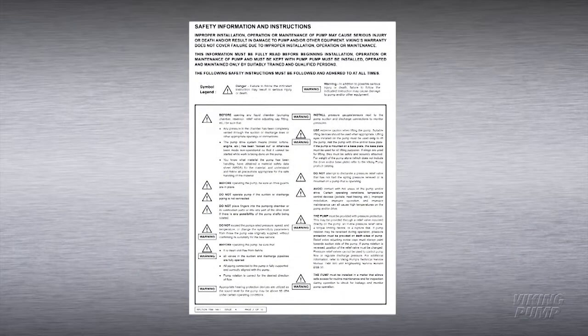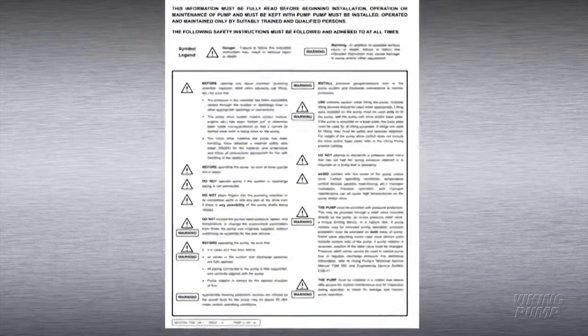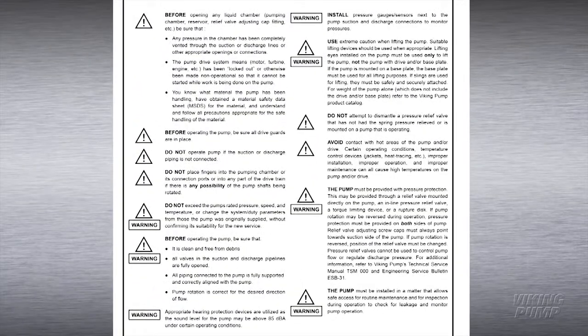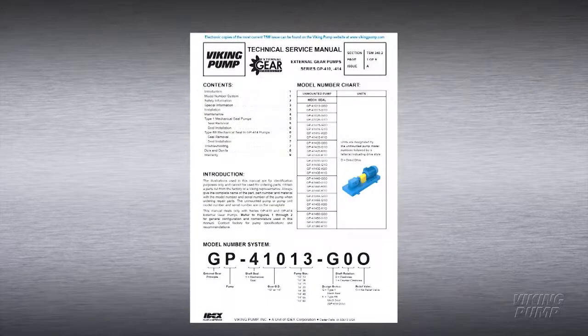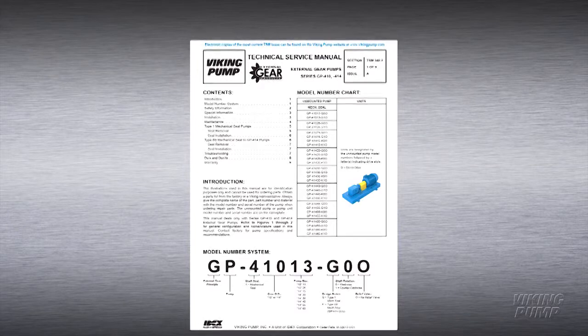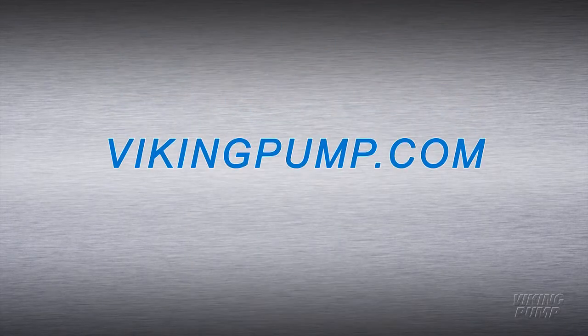As always, remember that safety is the highest priority. When working on or around any equipment, follow the correct safety procedures. It is critical to know what liquid the pump is handling and what precautions are necessary to safely handle the liquid. Always read and follow the safety warnings in the service manual before any work is started on the pump. Copies of the latest service manuals can be found on our website at vikingpump.com.